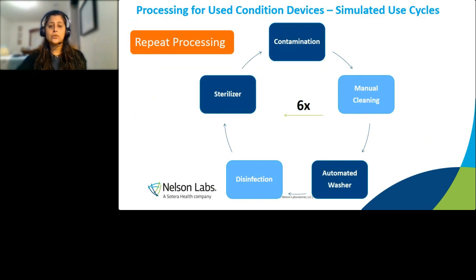Now, before we do the cleaning validation, there are cycles called simulated use cycles that are performed. These are called repeat processing, where we are processing the device multiple times to make them into, let's say, used conditions. What I mean by that is back in the day when I started, we didn't have this process. We would test medical devices that were straight out of the manufacturing box. It's shiny, it's pretty, looks very nice. And we did validations on those. So the possibility and the probability for it to pass is much higher than it would be if I cycle them for reuse cycles that you have to deal with every day.